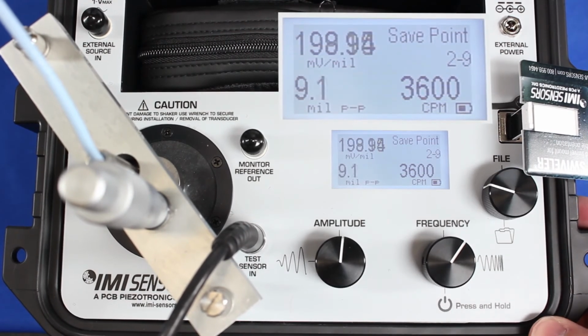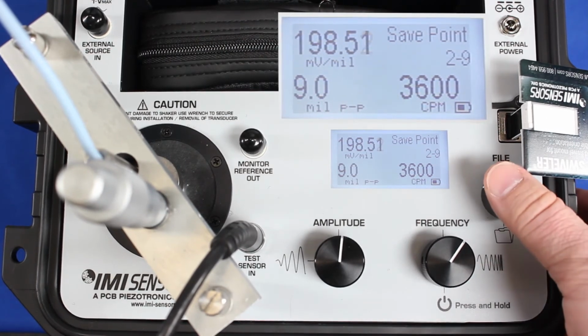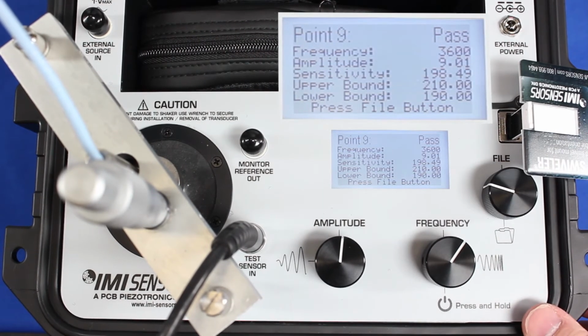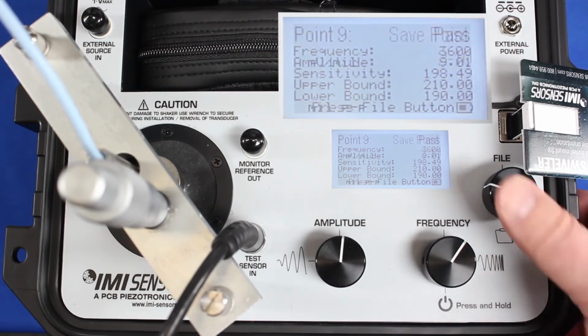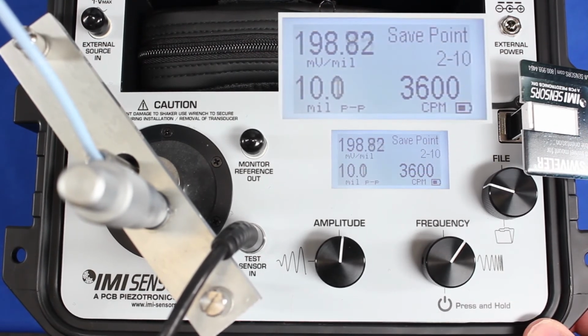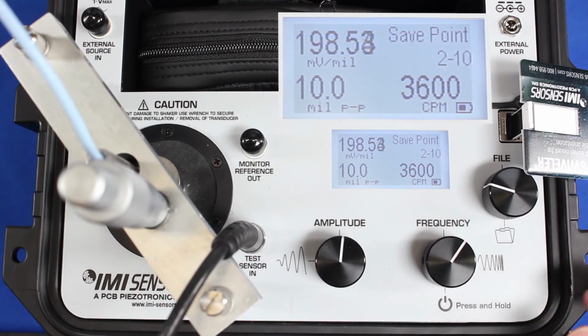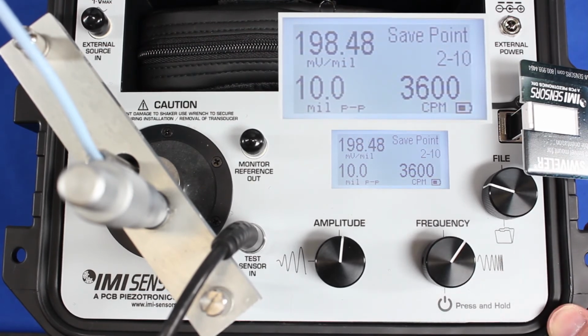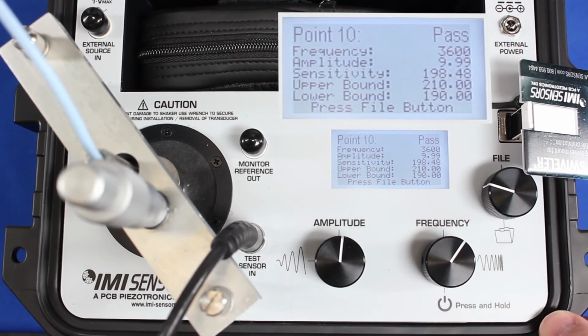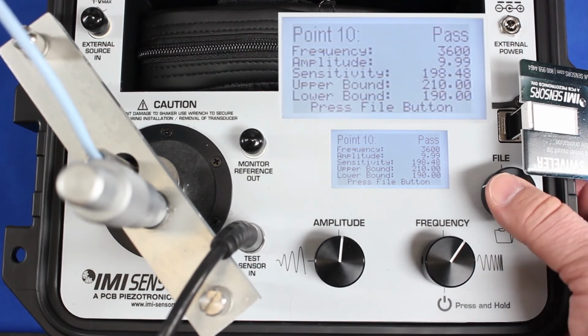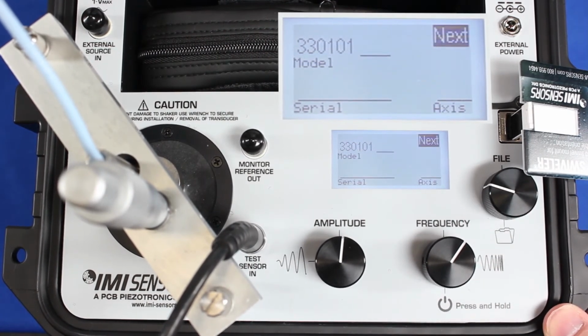9 mils. By the way, I always recommend that technicians test at the actual running speed of the machine on which the proximity probe is installed. So that's why I've chosen 3600 CPM. It's a typical running speed for a gas turbine. 198 millivolts per mil at 10 mils peak to peak, 3600 CPM is my final test point. And again, we pass. So I was notified after each point that my proximity probe is within tolerance and the calibration passes.